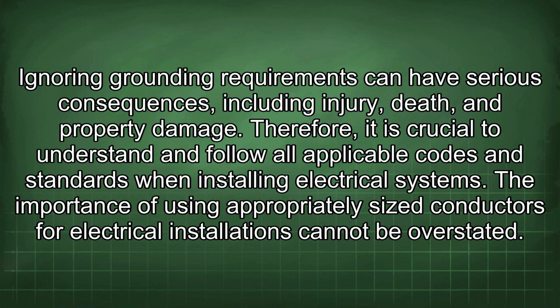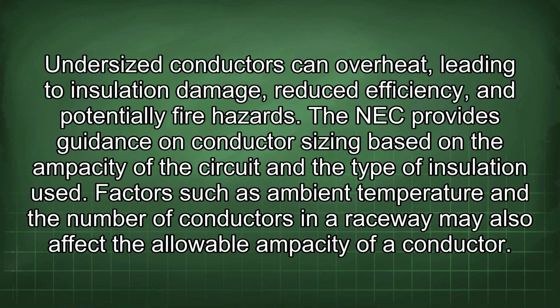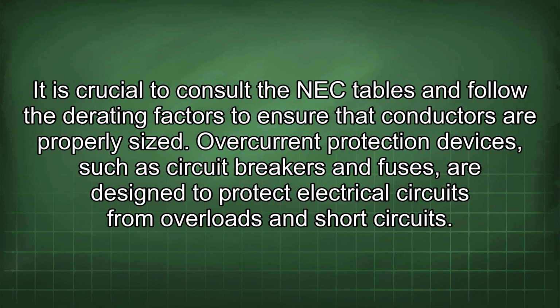The importance of using appropriately sized conductors for electrical installations cannot be overstated. Undersized conductors can overheat, leading to insulation damage, reduced efficiency, and potentially fire hazards. The NEC provides guidance on conductor sizing based on the ampacity of the circuit and the type of insulation used. Factors such as ambient temperature and the number of conductors in a raceway may also affect the allowable ampacity of a conductor. It is crucial to consult the NEC tables and follow the derating factors to ensure that conductors are properly sized.